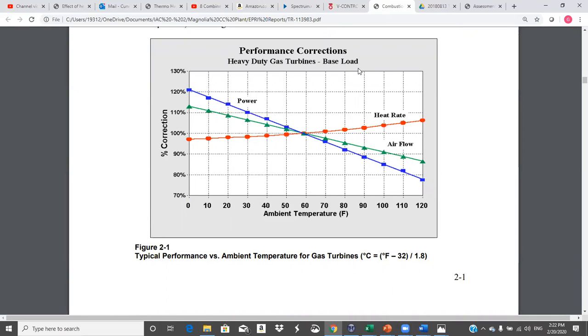And then, of course, you get over here in Vegas, if you're not doing any sort of cooling, it's 120 degrees outside, where's your power? Your power is down here at about 78, 77% of rated. Okay, so that's what this evaporative media is trying to do. It's trying to, in the summertime, when you lose capacity, let you do some evaporative cooling so you can boost the power output, help your performance.